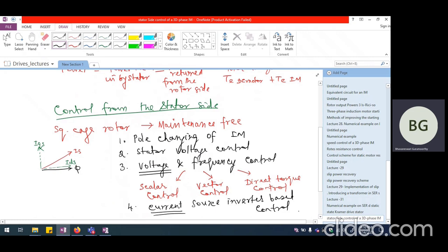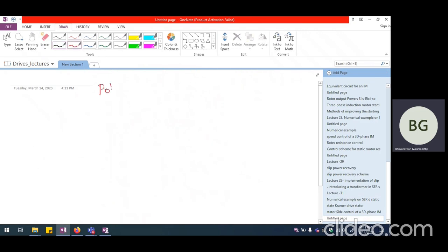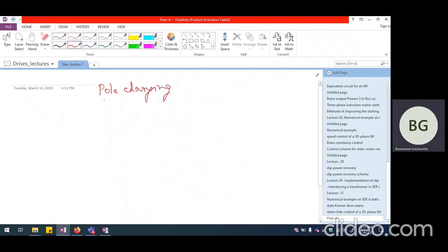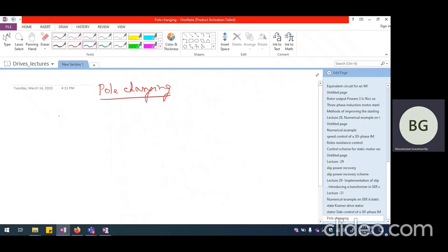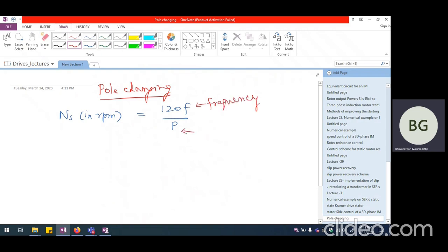So these are the four types of control we will talk about for stator side control. Let's now venture into stator side control starting from pole changing. In pole changing, the synchronous speed NS in RPM is 120F divided by P, where F is the frequency and P is the number of poles. If we keep the frequency constant, by increasing the number of poles we will be able to reduce the speed — this is the methodology behind pole changing.